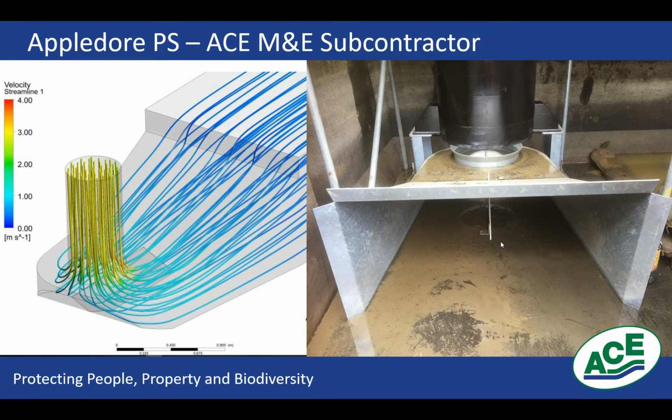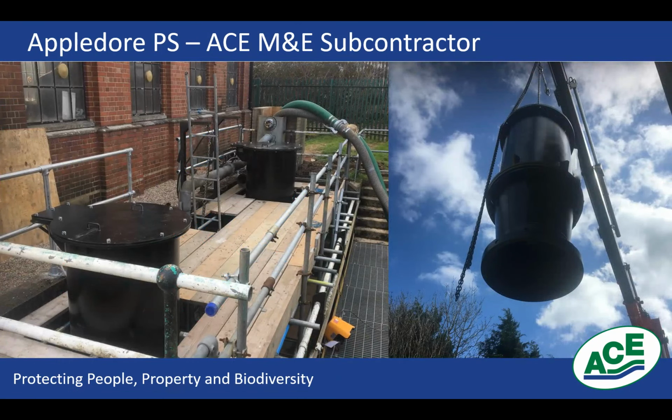We could then fabricate the FSI, the formed suction intake, which you can see here. And then we put the pump canisters on top, inserted the submersible pumps, and then also, of course, supplied the full control panel, complete with ABB variable speed drives. And it's very important with the variable speed drives for fish-friendly pumps, because if you go with a fixed speed drive, what you end up with is a pump that's not running as efficiently as it could be at all moments in time.